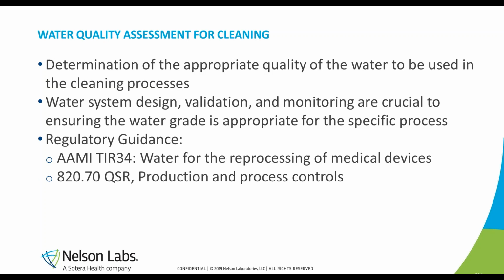The majority of reprocessing cleaning process steps are water-based, and therefore it is of significant importance to determine the appropriate quality of water to be used for the cleaning process. Water is considered the universal solvent because over time, water will dissolve most anything to which it is exposed. Because of this, water, even from a municipal source, will contain a significant amount of impurities. When selecting water quality for a given process, consider that the level of acceptable impurities is determined by the potential of that impurity to impact the product, the process, or the patient health. This understanding and potential impact of impurities is crucial in water system design, validation, and process controls.